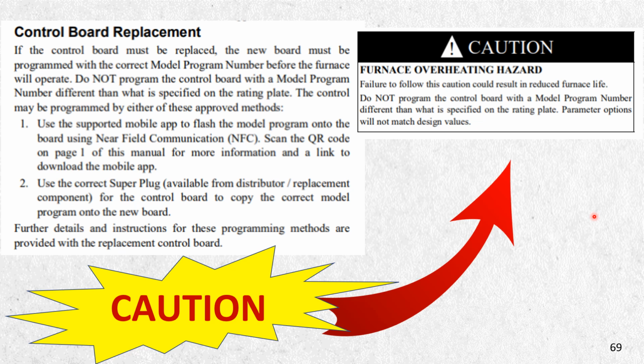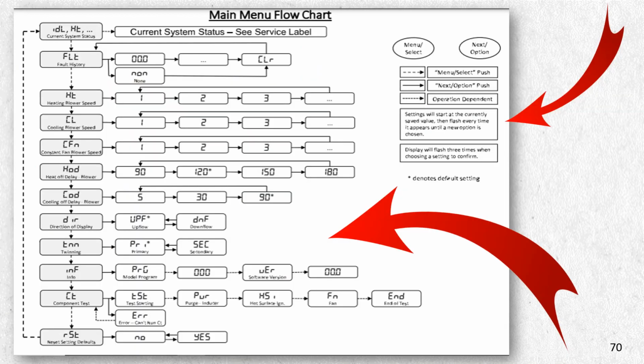And if you're going to replace the board, like I said, you've got to have the program number and the software update to make sure you do that. Don't just put a board out of the box and stick it on there and not even look to see if it's programmed. So make sure you have all that information before you swap it out. And you can do that, like I said, with no power on it. When you change the board out, or before you change the board out, you can still hook your cell phone to it, and it'll tell you what version and program number it is.